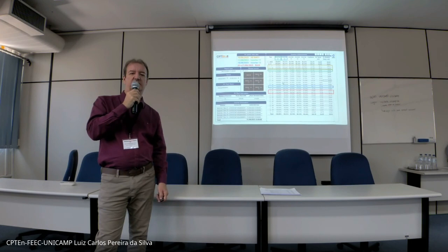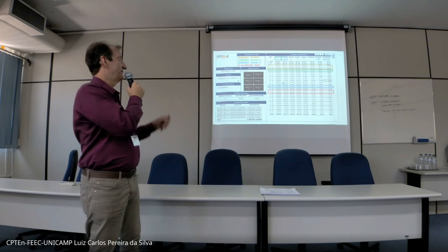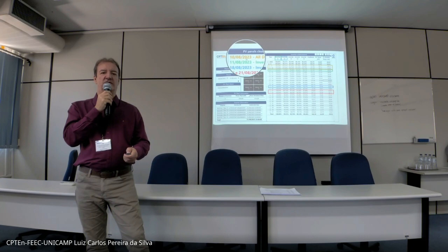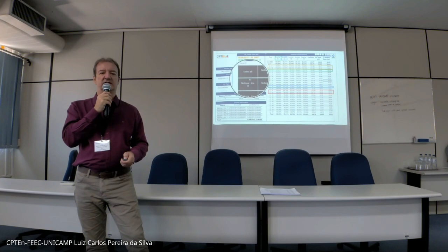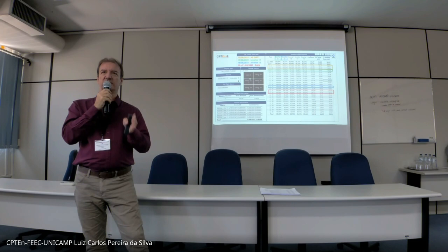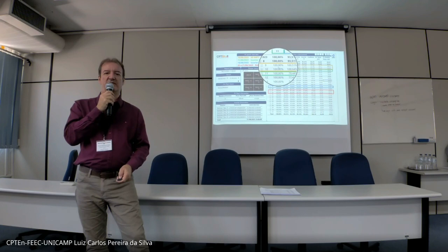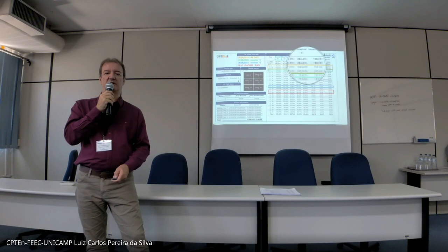Let's summarize it in one dashboard. It's maybe a very complex dashboard, but I will show you something to get your attention. Until August 10, all the PV modules are dirty. We select one of the inverters, inverter 11, as the main inverter, so it's a control sample. We will compare the other generation against inverter 11. Before, when everybody is dirty, they generate the same, 100. And on day 11, we clean the PV modules.